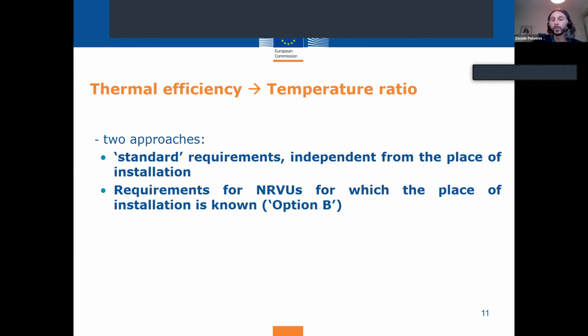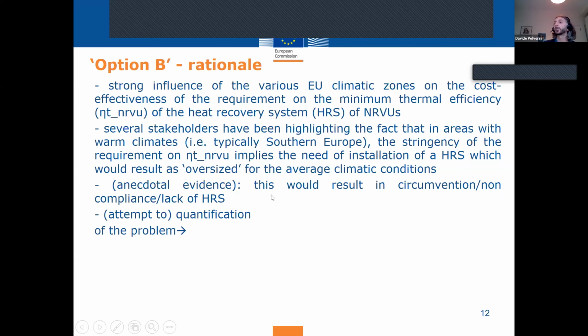So we would continue to propose this requirement in this way for those products which are, let's say, agnostic of the place of installation. So when the manufacturer does not know where the product will be installed, the requirement that will be applicable is one similar to the others, to the ones already in application. So a requirement on a fixed value. In the case, and we understand this can be typically the case for many non-residential ventilation units, in particular those of big size, in the case when the place of installation is known, we would propose to use another approach. A bit of a rationale for this.